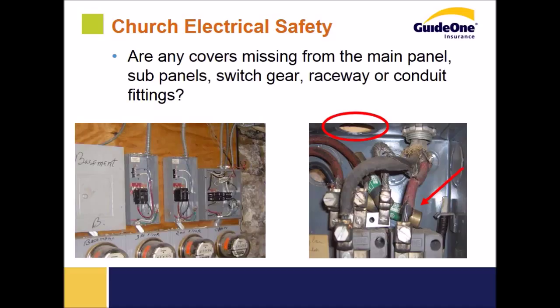Just a couple more obvious examples. On the left, we've got covers missing, and those covers are needed to prevent dirt, dust, moisture, and physical damage, as well as electrocution. And then the image on the right, this is a little hard to see, but you can see the knockout at the top has been taken out. Whether this box was repurposed and they simply didn't put a blank in place to cover that hole, or whether the electrician took out the wrong knockout when he made this installation, it has created a problem, because now some cartridge fuses have fallen through that hole and could cause a very serious problem. They could cause a short, they could cause an arc flash, they could cause a fire. So again, this is why we really need an electrician to come in and look at our systems.